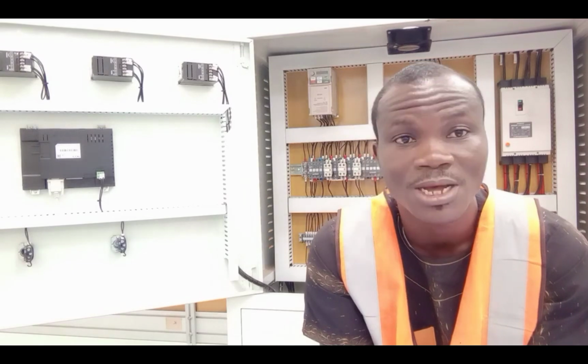And that is done to make sure that, to some extent, all the loads in the circuit have some kind of protection against excessive current, because the amount of current that will cause a lamp to blow will not even be enough for a pressing iron to start working. And so if we are talking of protection, we cannot connect both the lights and the sockets in the same circuit. So in every electrical installation, there is a distribution board or a consumer unit which houses the breakers that protect the individual circuits in the wiring.